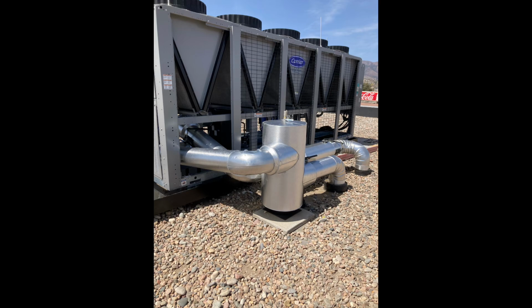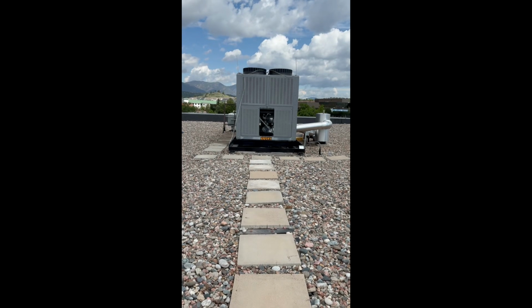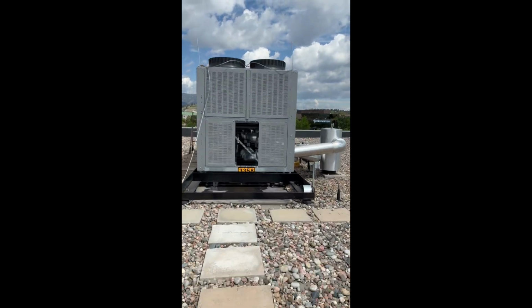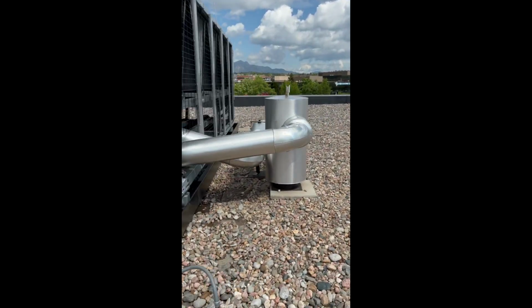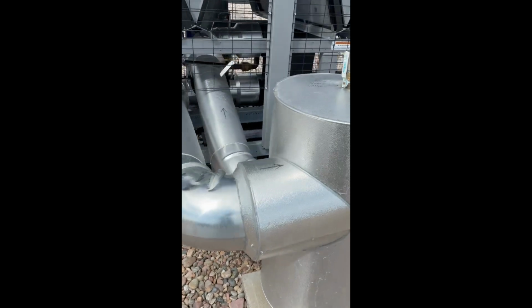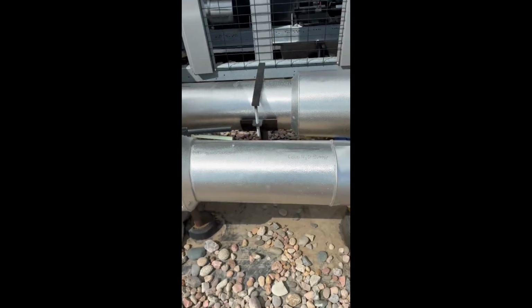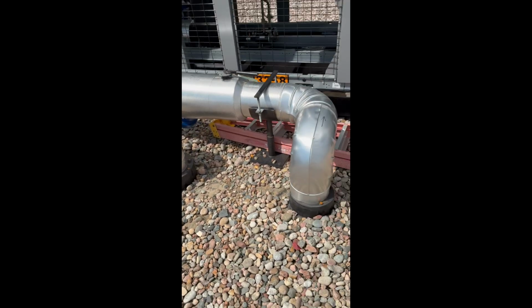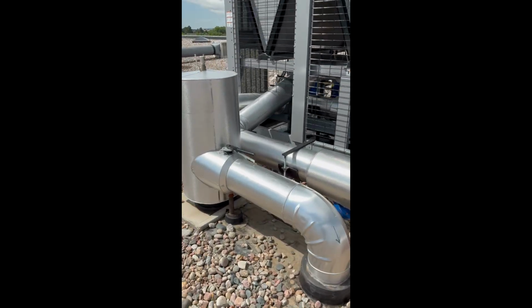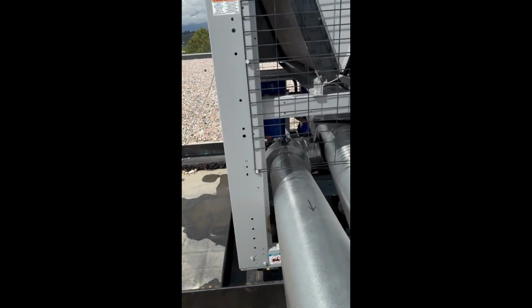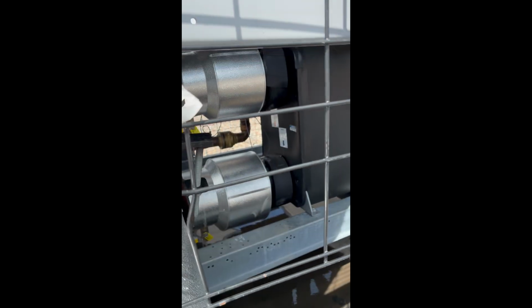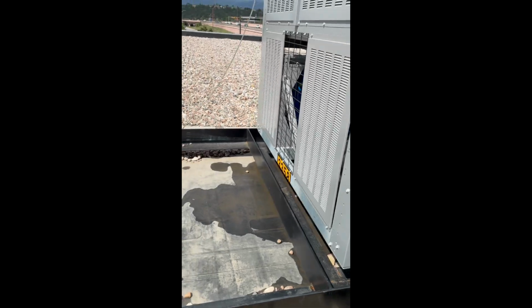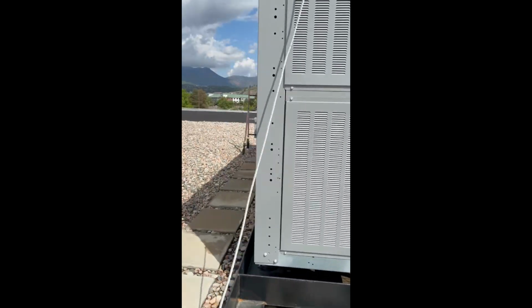They'll hook up the piping, they'll insulate the piping. I'll give you a tour. So here it is hooked up. It's got the inlet outlet piping hooked up. That's the air separator there. That was a requirement. So these pipes go down to the basement. So you got your inlet and outlet. And it's a plate type heat exchanger on this instead of the old shell and tube like the old one had. So much more compact.